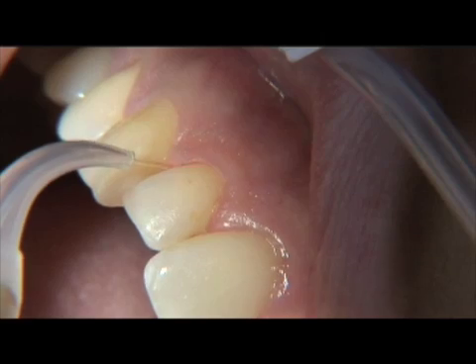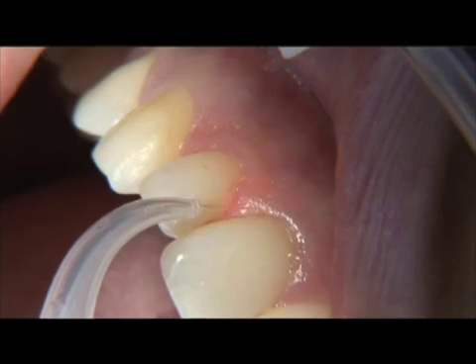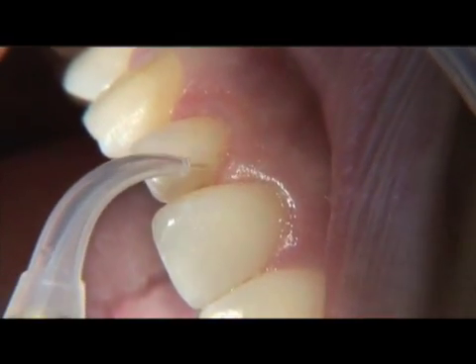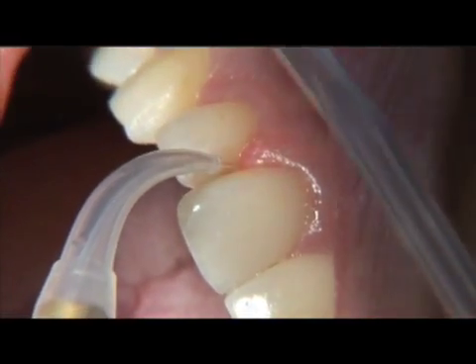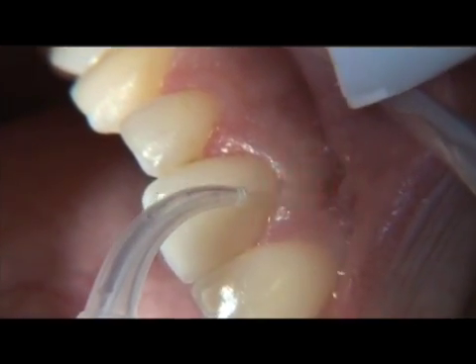Start with a setting of 1.0 watts. Use the minimum amount of power required to reach your treatment objectives. Start with the lower power settings for the procedure that you are performing, and increase power only as needed.